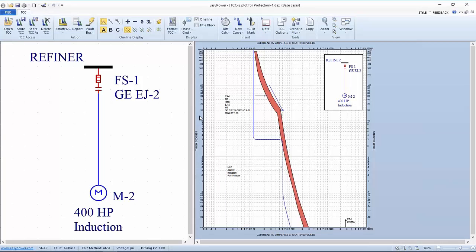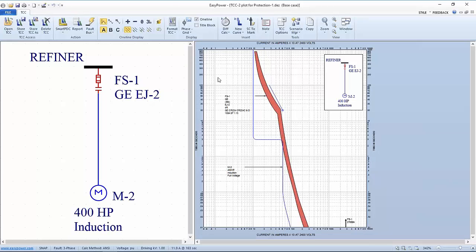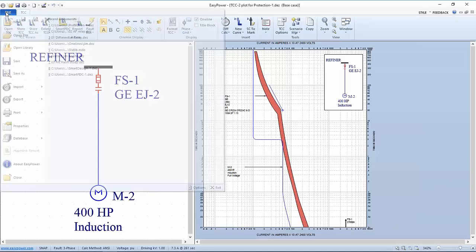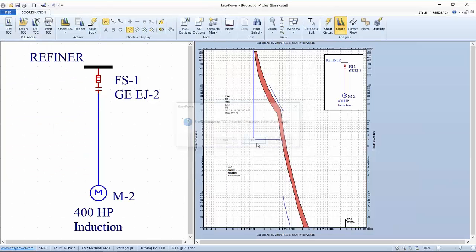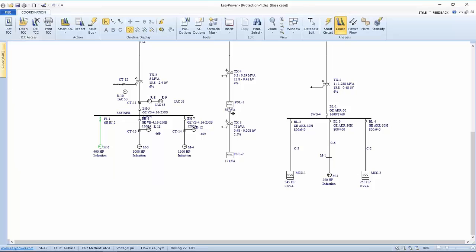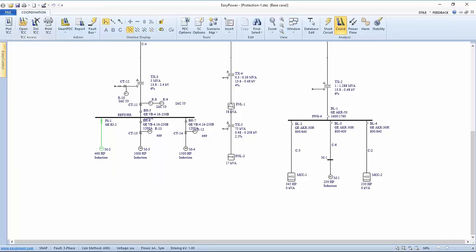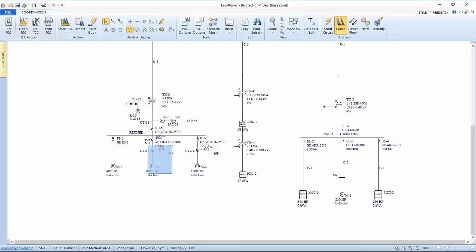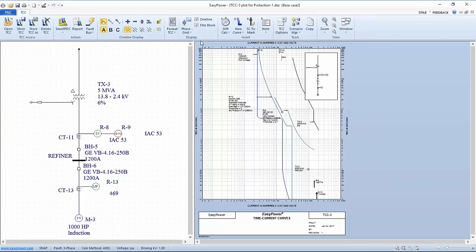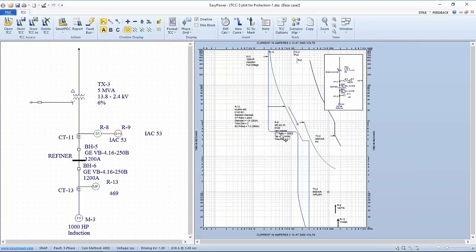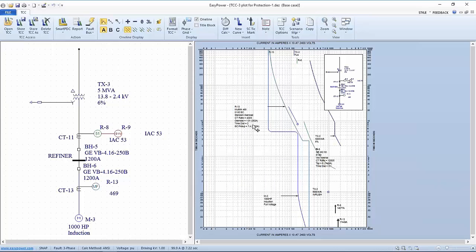If I open up the setup dialog, temporary setup dialog, for this case we call it a fused switch, we can see that the manufacturer's type and style determines what this curve is going to be. If we pick a different size curve, you can see that it's going to apply. The lower part of this curve is the fuse. The upper part is the overload, motor overload. If we pick a different size, it will plot differently when it comes to the curve.